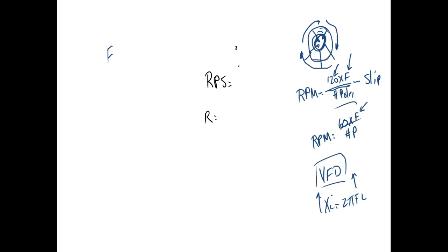You take the voltage divided by the frequency, and if you maintain that voltage per hertz ratio, then you can control the speed of that AC motor over a wide range. DC motors, all we have to do is just change the voltage to the armature. And if I increase the voltage, what does it do? Yeah. And by George, DC motors, you can make them suckers scream until they sling themselves apart.